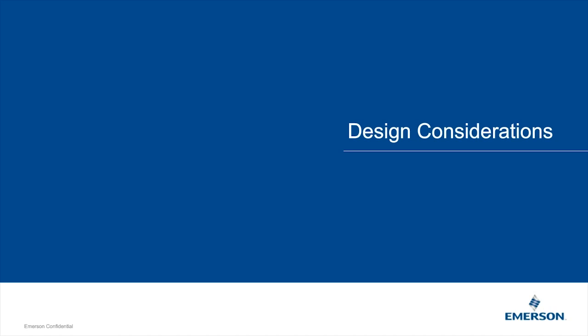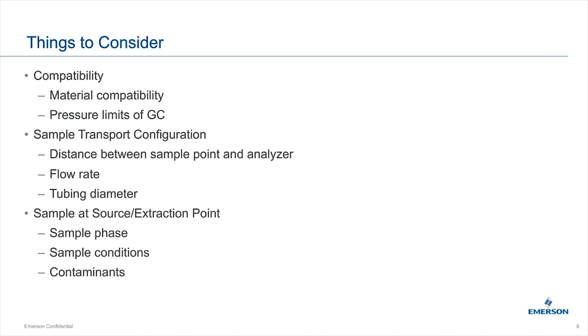Moving on to design considerations. Compatibility always comes up — whether you're running a liquid or a gas, there are many components in the sample handling system and potential interactions. For example, we normally recommend 316 stainless steel, but if you have H2S at certain concentrations or greater, we recommend silica-coated tubing instead. Pressure limits: you could be running at several hundred PSI in your pipe while the GC can only withstand 10 to 30 PSI at sample injection. Sample transportation configuration also matters — where your GC is placed versus the probe or sample point. We always recommend getting the GC as close to the probe as possible.